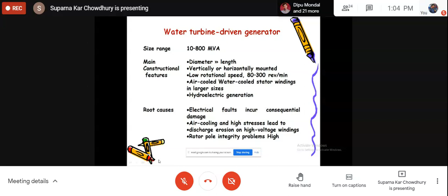These machines are normally air cooled. For larger sizes, the current rating is large, so we can have direct water cooling for the stator winding. They are used for hydroelectric generation. Their root causes of failure are electrical faults, as usual, then air cooling and high stress leads to discharge erosion on high voltage winding. Rotor pole integrity problems: the number of poles is high, and you know the construction, the poles are assembled on a spider, so that is a problem if there is a disjoint or anything.